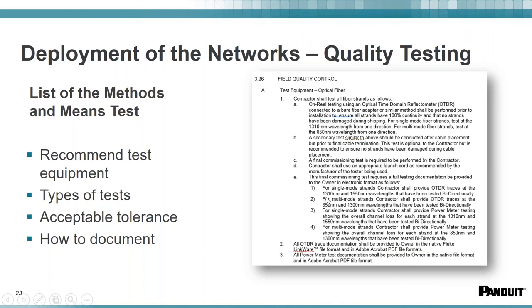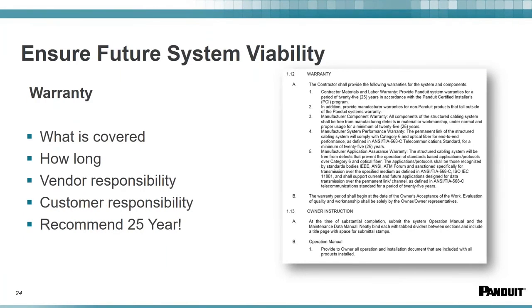Similarly, when doing viability testing, once you have all your test results, you need a set of guidelines that confirms the system you designed and tested passes the limits for your communication, and that the media chosen abides by TIA 1005 specs and all the MICE categorization for cable and connector types—whether you need a decode connector or a straight-through RJ45. With all of that, you have complete documentation showing a complete system that is survivable and will last for a certain number of years.